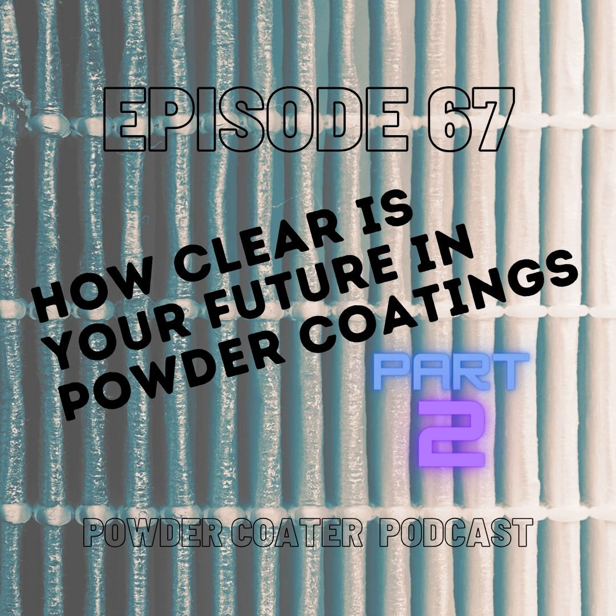Electric is so fast that conduction never plays a role. That's the reason you don't really see electric on the cure side unless it's one part in the oven. It might have a chain on edge where it's rotating, where the oven is designed for the part. But in what you do for a living, your job shop, you're basically never going to see an electric infrared cure oven. Now you can obviously do electric cure oven in convection, but you typically only see that in batch, because it would be too expensive to do it in a flow through larger environment.